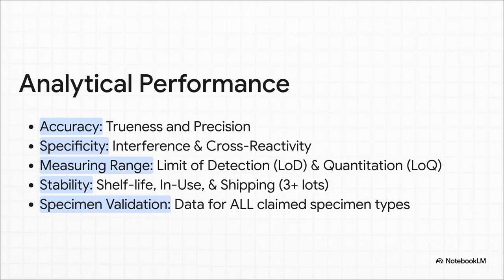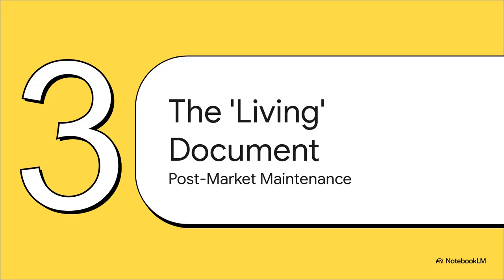And stability, this is a big one. You need data proving it works for its entire shelf life, while it's in use, and after being shipped. And you need that for at least 3 different manufacturing lots. Oh, and if your label says it works on multiple specimen types, you need full validation data for every single one.